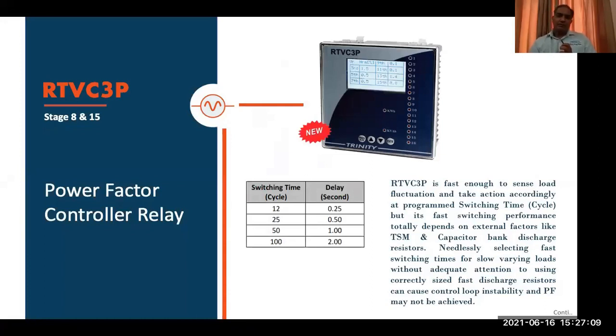So now most of our customers were also making RTPFC panels, like a real-time power factor correction panel. For a real-time power factor correction, we need a relay which can switch in real time. When I talk of real time, I mean switching in milliseconds. A standard APFC relay which we have has a switching delay of minimum 2 seconds. So below 2 seconds it cannot switch. And so what about those panels which need switching below 2 seconds?